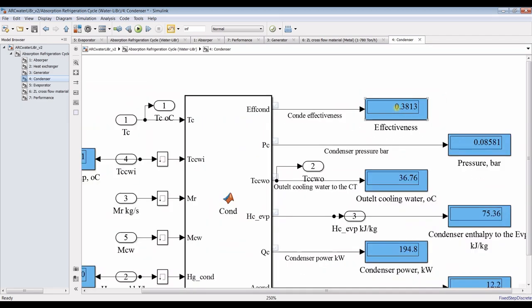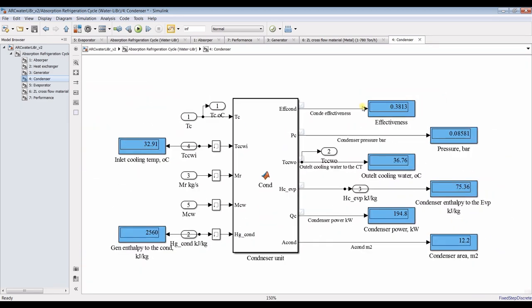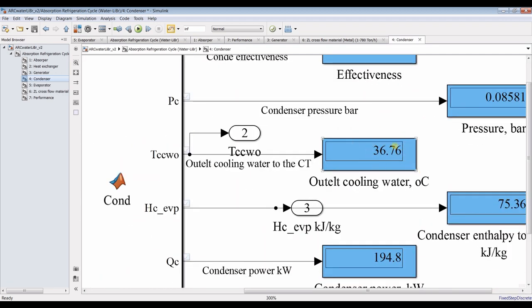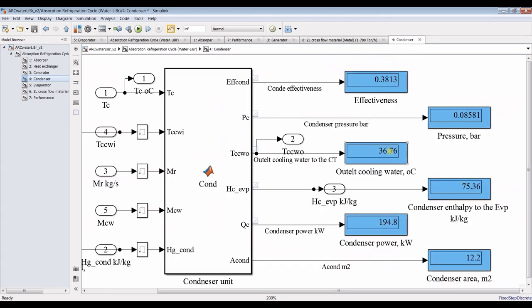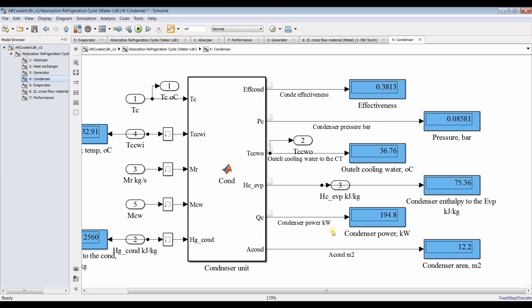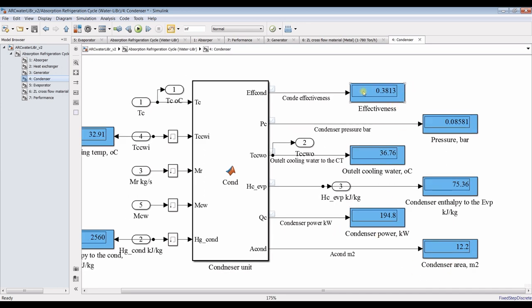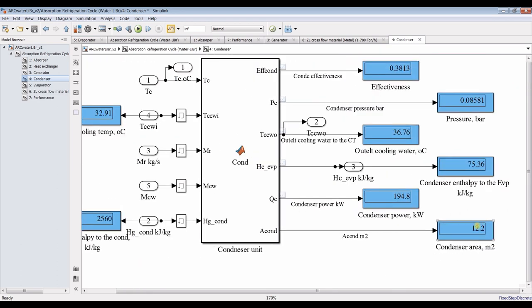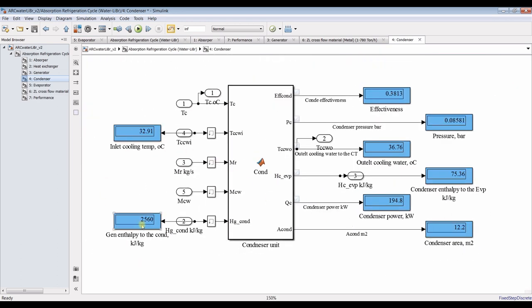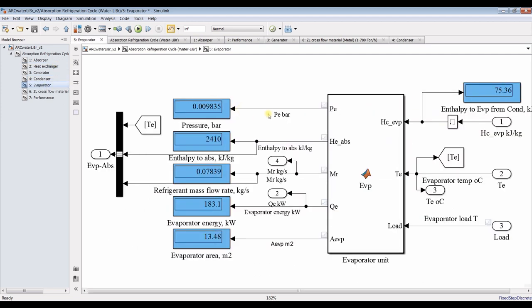Our condenser effectiveness is around 38%. We can control some outputs to change or increase effectiveness by controlling the temperature. This is the final outlet cooling water temperature going to the cooling tower and condenser. Condenser power and condenser area — note that lower effectiveness means a higher surface area. For the evaporator, we have pressure, a recycle stream, thermal power, and area of the evaporator.